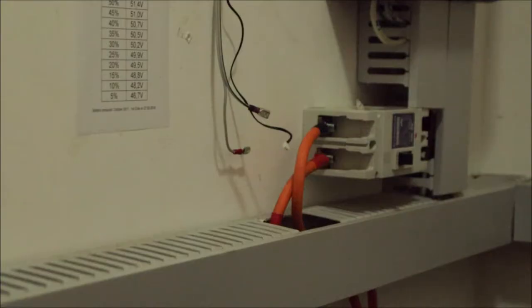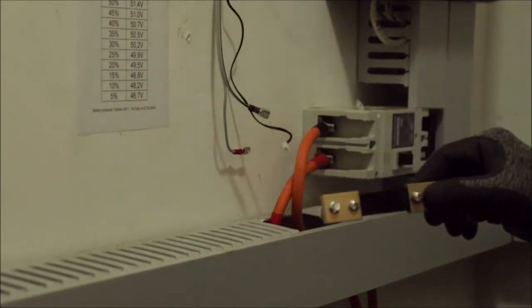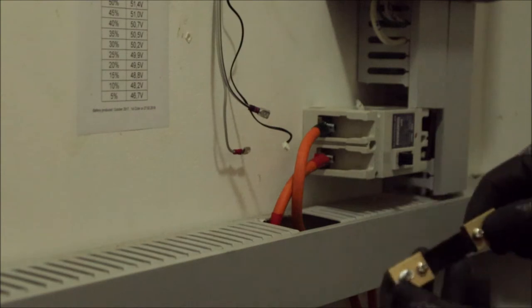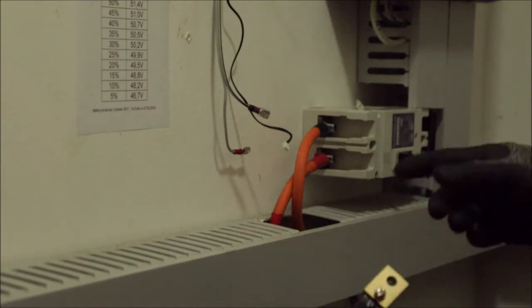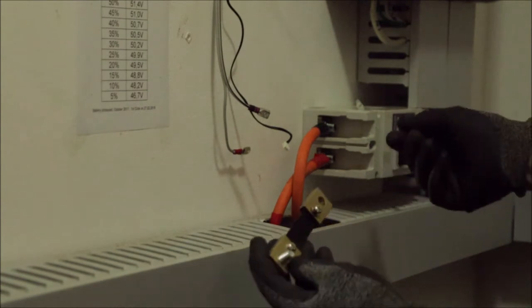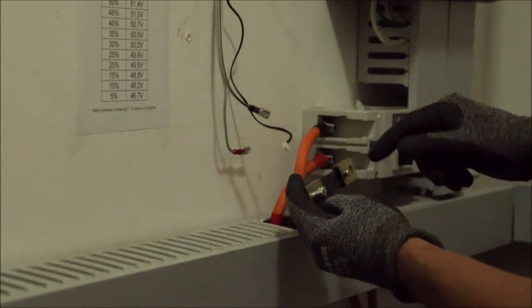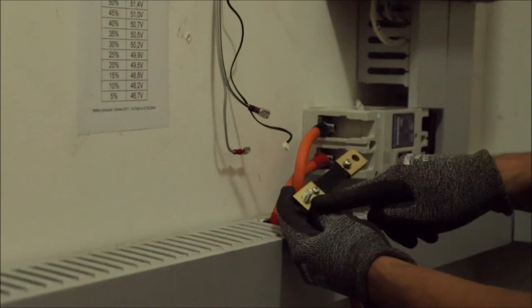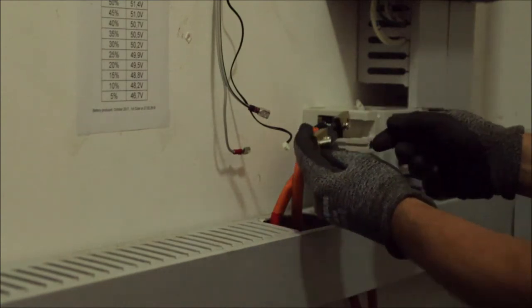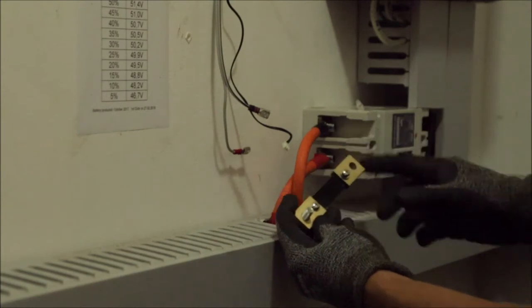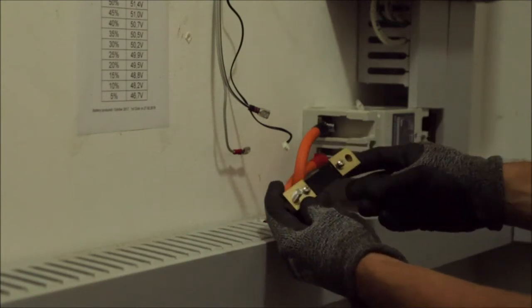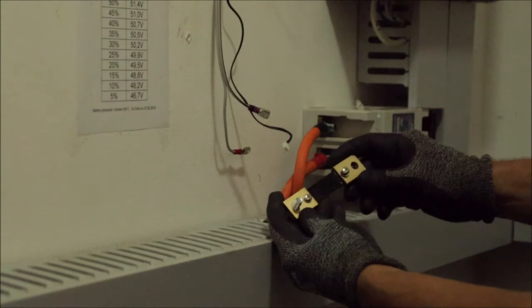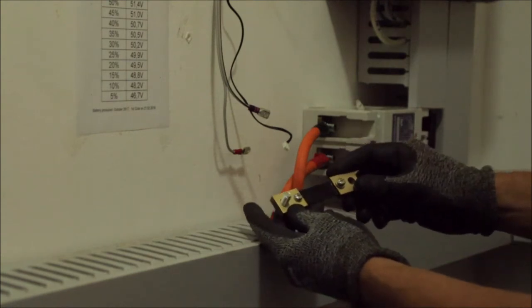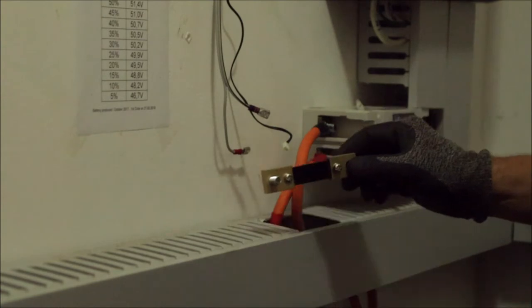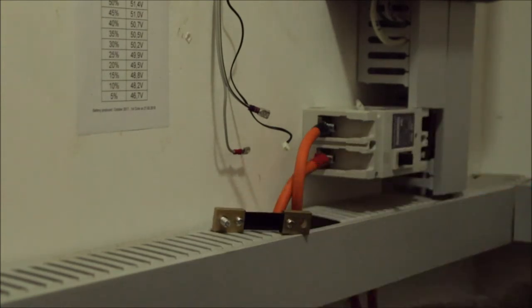So what I'm going to do now is remove the negative cable from the breaker and install the shunt. And I want to do it while the inverter is still running, because I don't want to power it down because of the cap. So I will just open up the screw and remove this very quickly and immediately put the wire on the screw here, and the other one also connects to the breaker. So without too much interruption, I think 1 second should be okay and still work without shutting down the inverter. So let's try this.